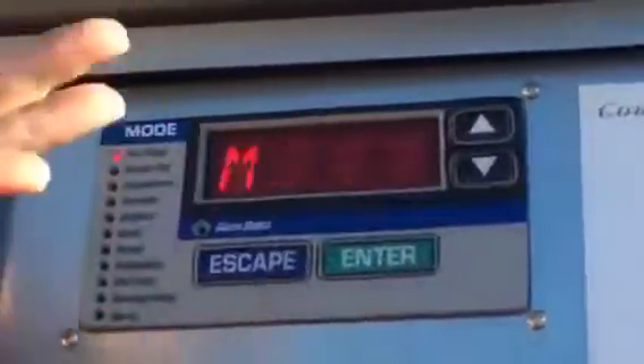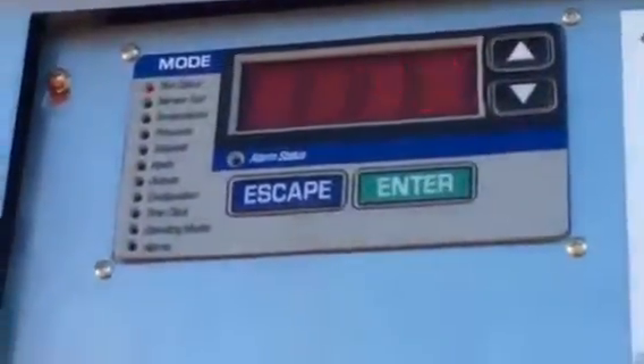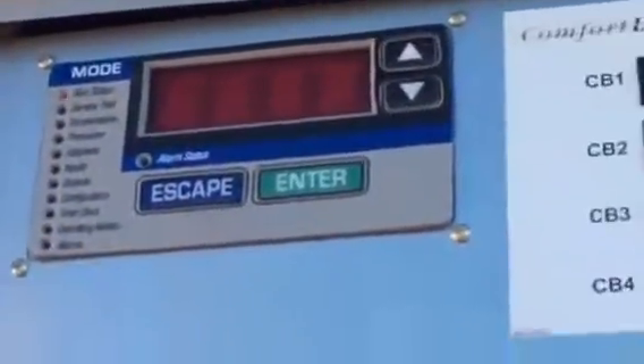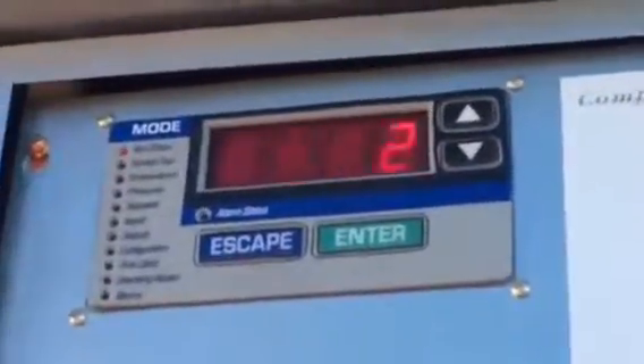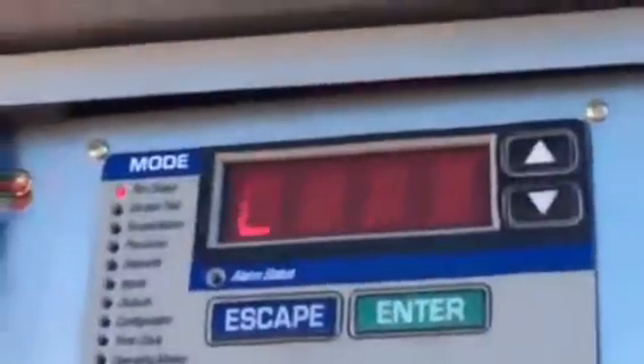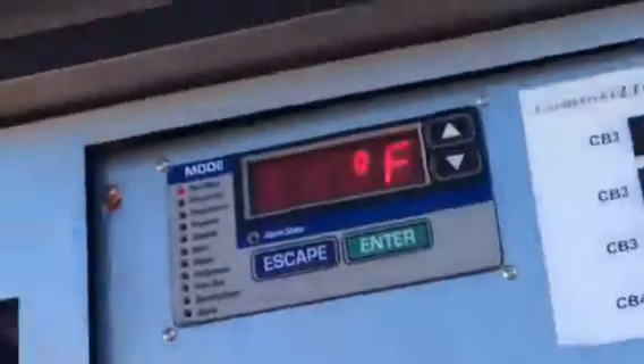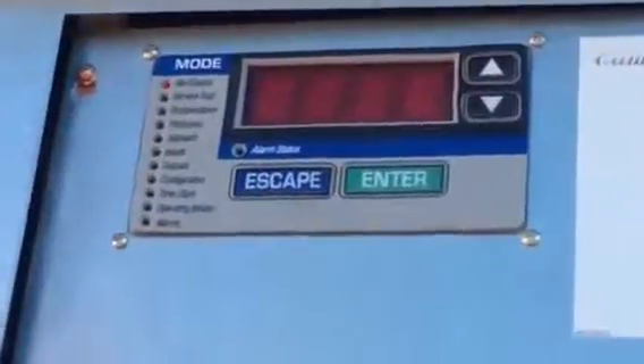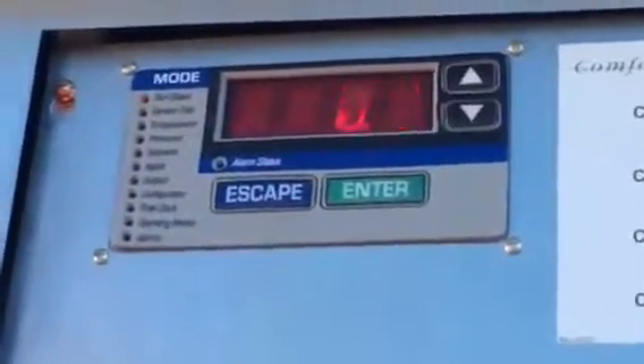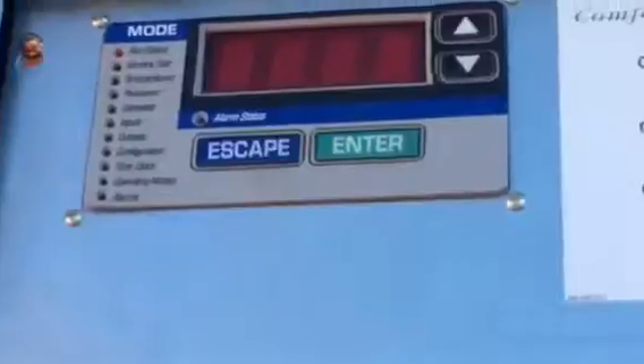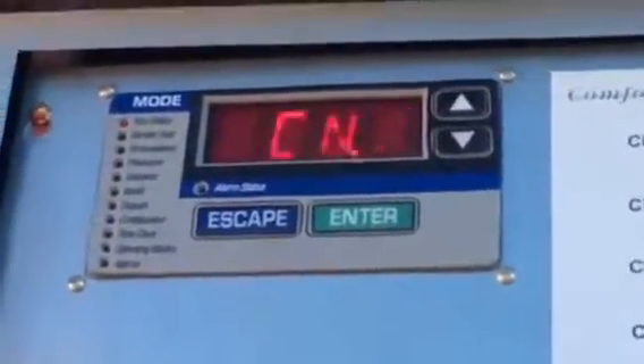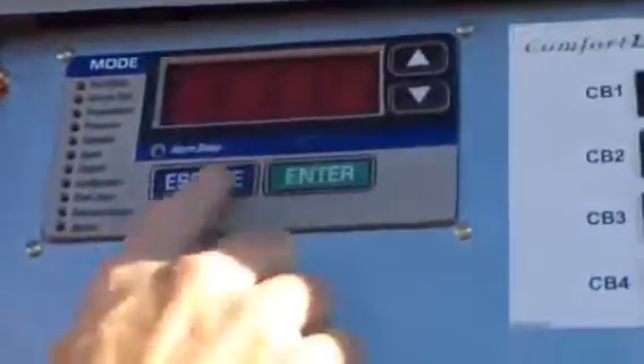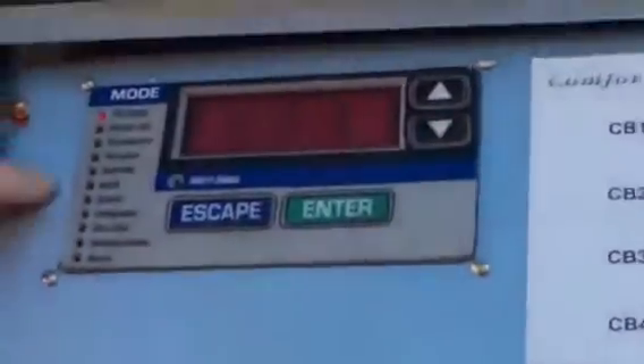We just showed that blinking light, the force was on the actuator, like the economizer. We can go in and calibrate it with this through the marquee, force it to run 0 to 100% so it learns its position, and it may come back that the calibration failed. It can't, which would be an indication I may have a problem with the actuator. And manually, I can always go in and force it to a certain position also. And that's things like, let's back out. I have inputs and outputs. I can always choose to see what kind of inputs the machine is looking at and receiving.